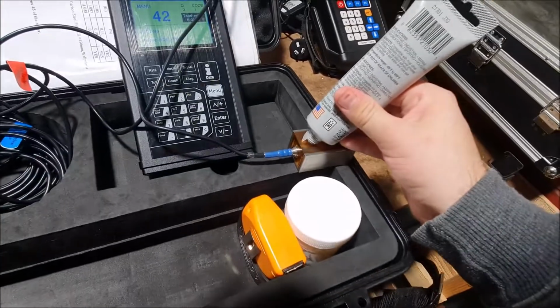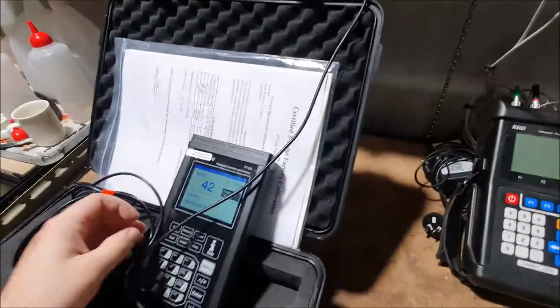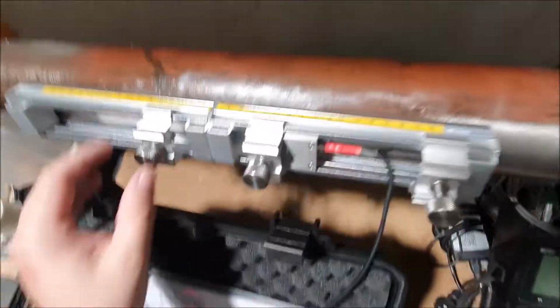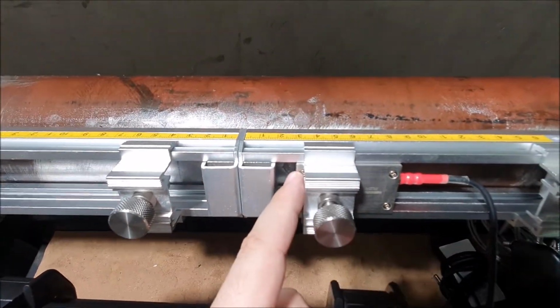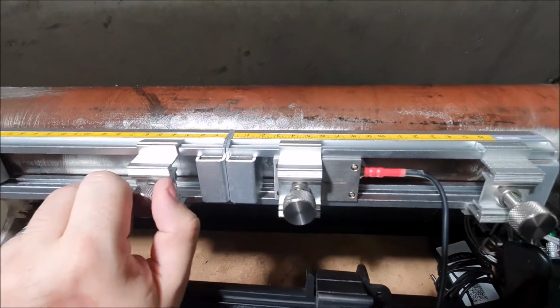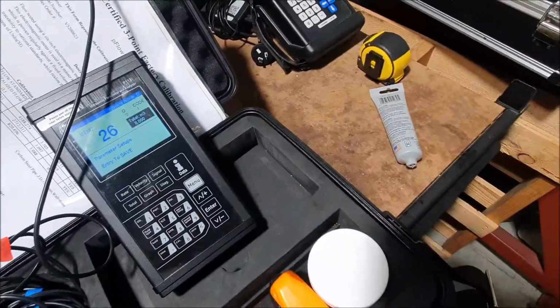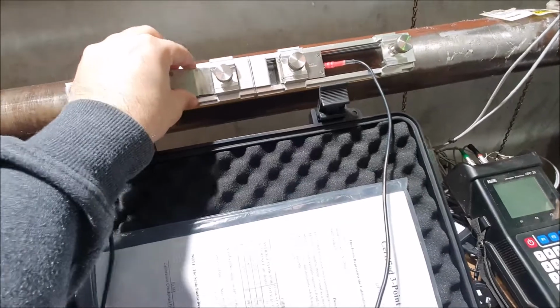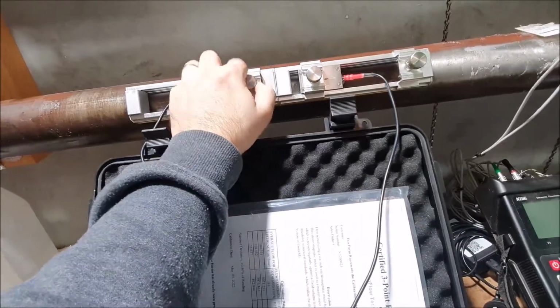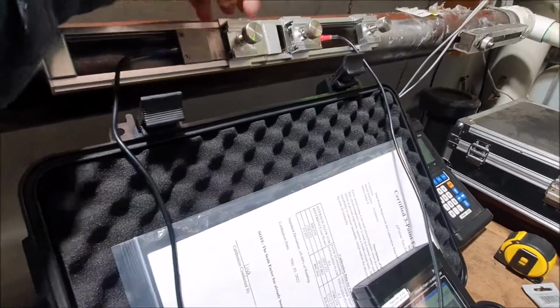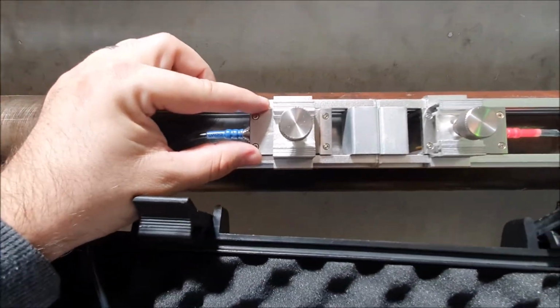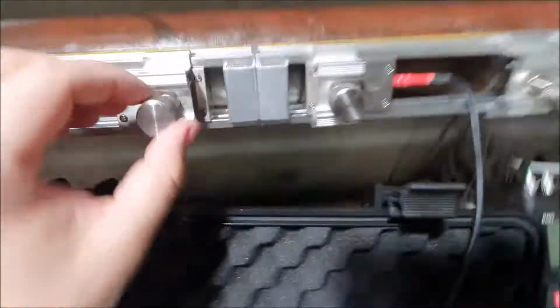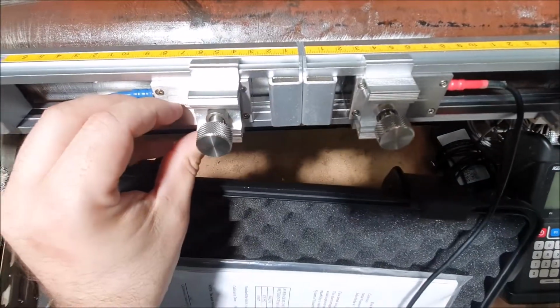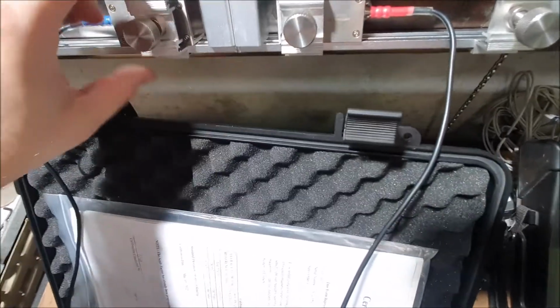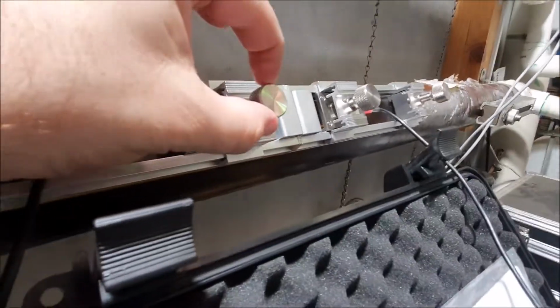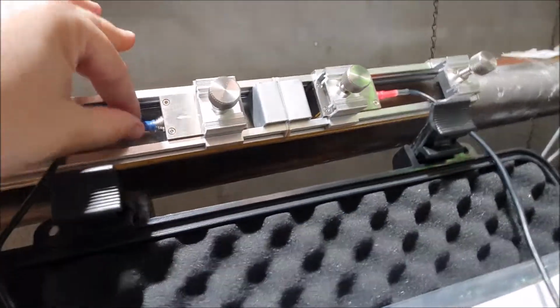So I'm just going to grab some couplant, put a nice blob on it. Okay, and we needed, what was it, 60.5. So we've got 3 centimeters. That's to the face of the transducer. And I'm just going to do the same on this one. Okay. Slide this into position. The transducer at about 3, and we're just tightening it down, so the total distance there is 60 and a half is what we actually need. And you'll see those little bits tighten down onto the transducer and just make everything nice tight and snug.